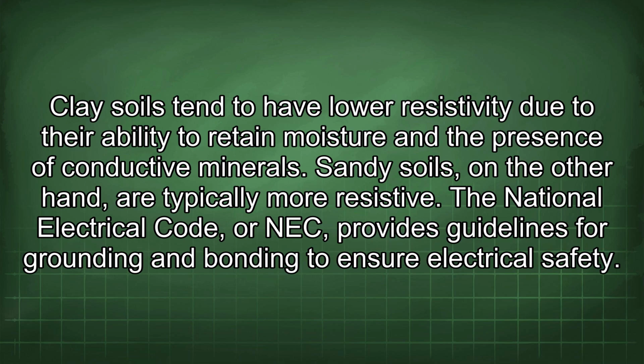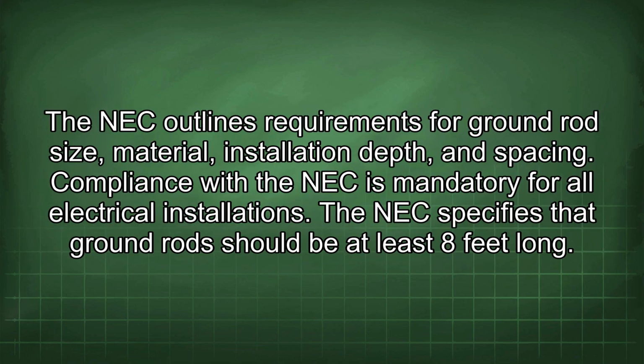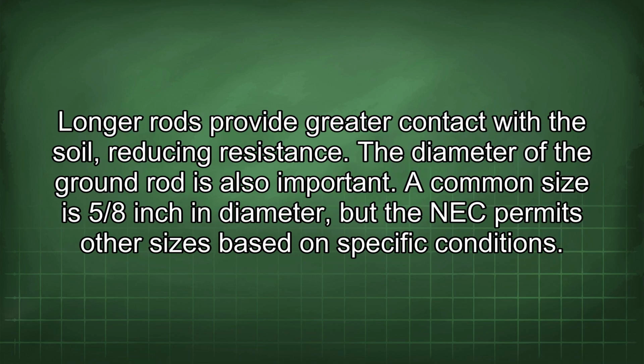The National Electrical Code, or NEC, provides guidelines for grounding and bonding to ensure electrical safety. The NEC outlines requirements for ground rod size, material, installation depth, and spacing. Compliance with the NEC is mandatory for all electrical installations. The NEC specifies that ground rods should be at least 8 feet long. Longer rods provide greater contact with the soil, reducing resistance.